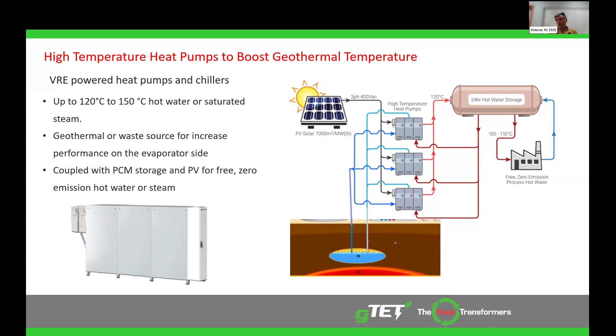Before I get into those details, just a bit about the general principles. Using a geothermal resource alongside variable renewable energies, we can take that resource and pump the heat up to 120 degrees, no problem. And now, with better higher temperature heat pumps available, we can go to 150 degrees saturated steam. Once we've got it up at that temperature for industrial use, we'll generally store the heat because the industrial demand is a bit variable.